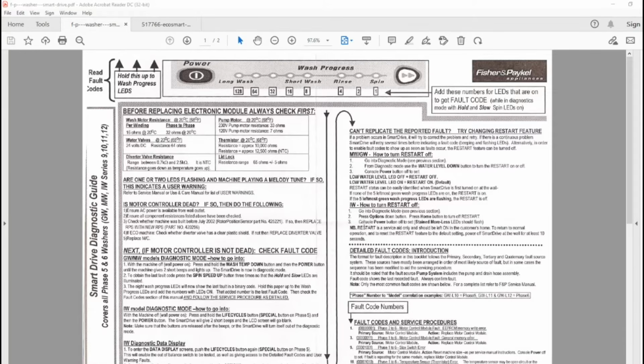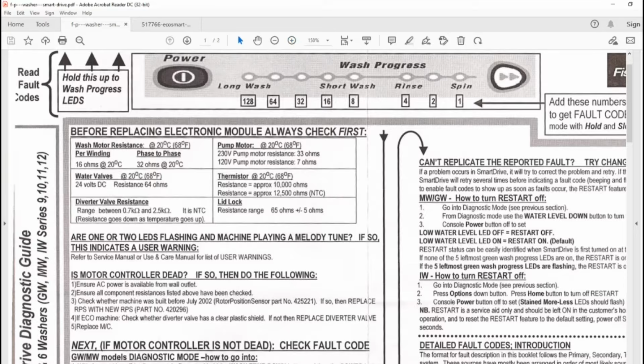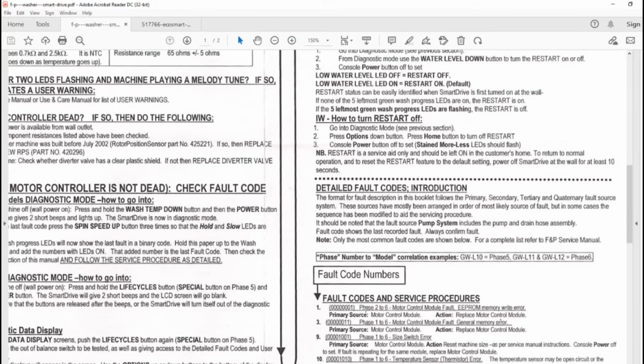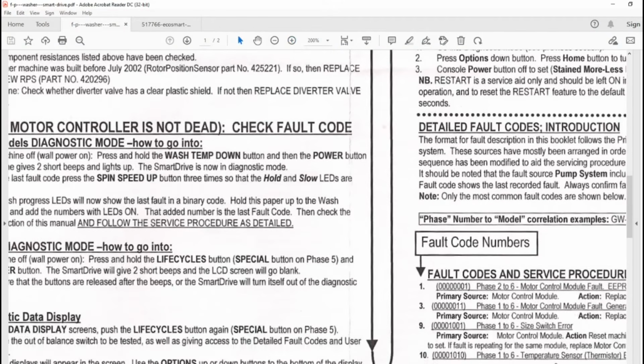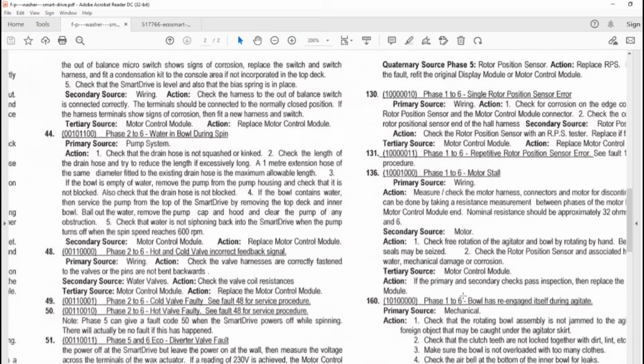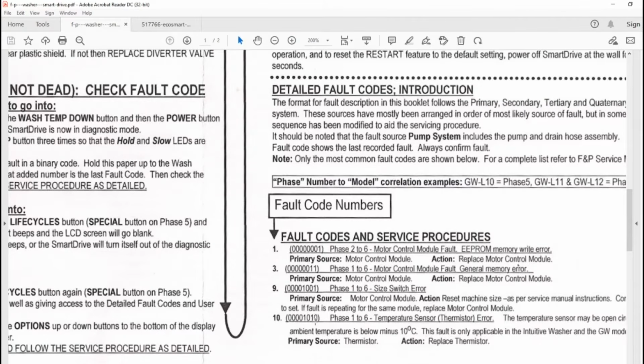This piece of paper here, I've got a PDF of on my screen. You can find it online with a bit of Googling, or it comes with the new control boards. And this has just got an abbreviated list of fault codes. It has got some resistances, etc. up here. And we're going to talk about the detailed fault codes. Now what it does is it's got the number, and then beside it you can see where it's got 0, 1, 1, 1, 0, etc. Basically where it says 0 is a light off, and where it says 1 is a light on. So rather than actually having to figure out exactly what code it is, you can just go by the lights being off or on and match up the pattern.